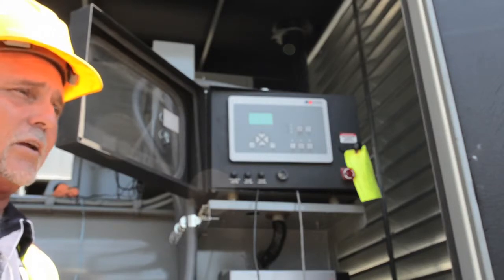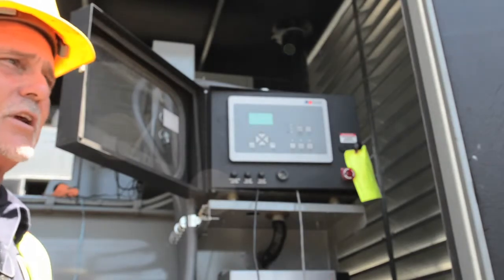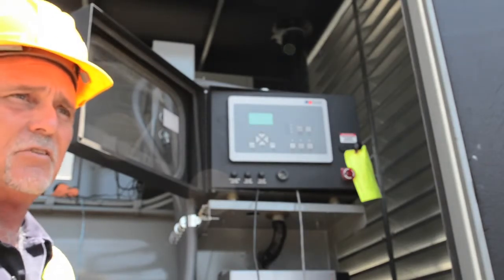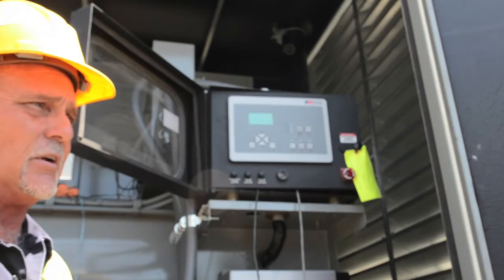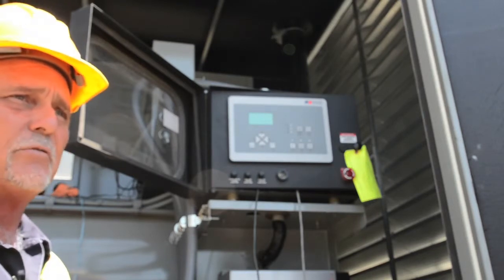And if you run it like that for, let's say, 2 years straight, and all of a sudden you hit a real serious power outage, and you run this generator for 8 or 10 hours, it's burnt 5 gallons of oil.